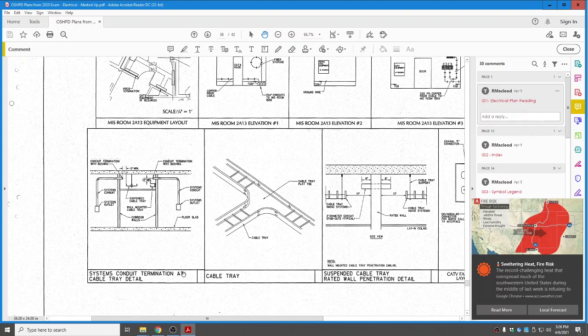Typical systems conduit termination at cable tray detail. So in the corridor we've got a cable tray. In some of the rooms or other spaces we have a conduit that stubs into the above ceiling space in the corridor or hallway where the cable tray is located, and then these cables just drop right into this cable tray and just run the length of the cable to wherever it's going. These are just stub outs through probably the corridor wall. They get fire stopped. They come in just above the cable tray, approximately 12 inches up from the cable tray, and just drop into this tray. All right, let's jump to the next page.